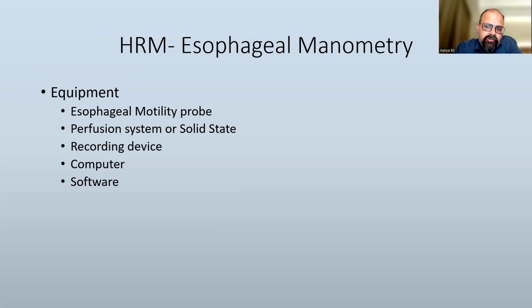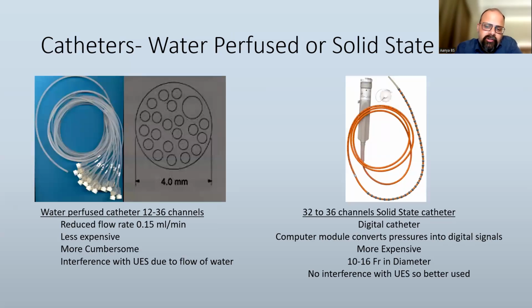The problem is that if you're using different perfusion systems, you will have a difficult time normalizing the readings across the equipment. Whereas if you use solid state equipment, it is more or less standardized. That's why the Chicago classification for esophageal manometry really harps on using solid state equipment with impedance recording. But practically, across India and across the world, there are many more water perfusion systems than solid state systems. So let's talk about all this equipment one by one. The first is your catheter, which, as I told you, can be water perfused or solid state.